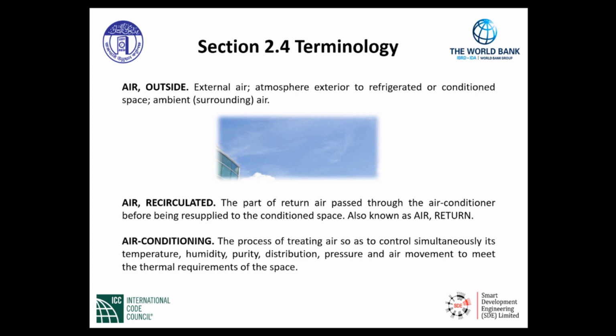Recirculated air is in fact the part of return air passed through the air conditioner before being resupplied to the conditioned space. We also know this as return air. Air conditioning is defined as the process of treating air so as to control simultaneously its temperature, humidity, purity, distribution, pressure, and air movement to meet the thermal requirements of the space.